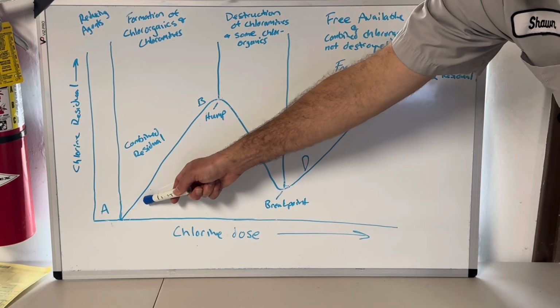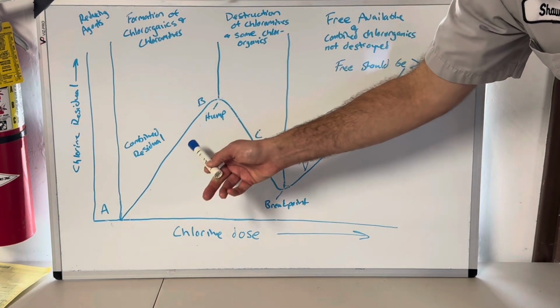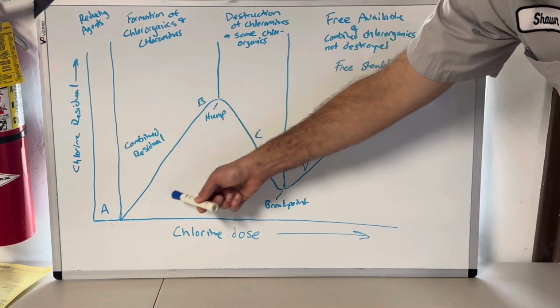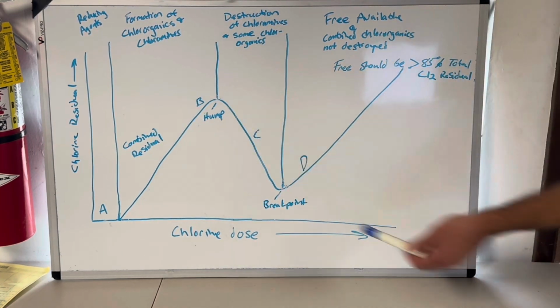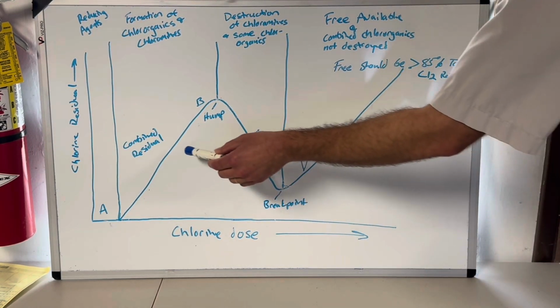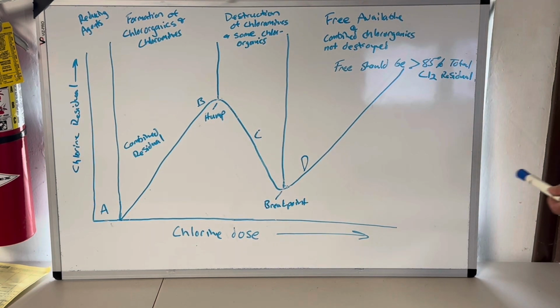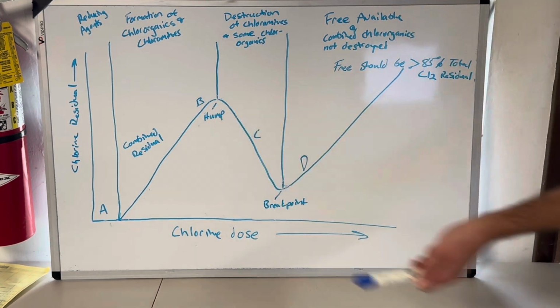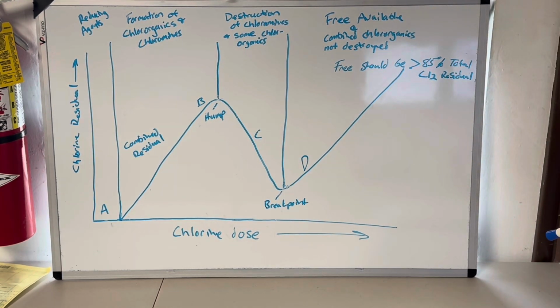As I continued to add total chlorine after my reducing agents are resolved, I may have ammonia present. Now, drinking water plants, you're adding aqueous ammonia here if you're using chloramines. But in a wastewater plant that's not nitrifying completely, or nitrifying at all, you're going to have some ammonia there. Now, I got quite a bit of ammonia in my trickling filter effluent.